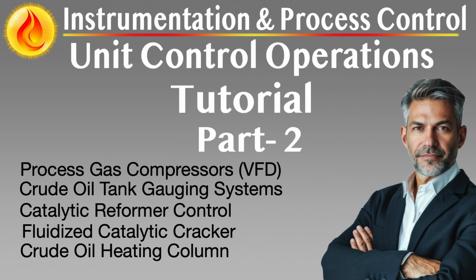Temperature control in the column is typically achieved through furnace outlet temperature manipulation, guided by feedback from column internal trays or flash zone sensors. Smart temperature profiling with multiple thermocouple levels allows the control system to infer vapor load and entrainment risk, enabling fine-tuned adjustments to heat input. This is especially critical to avoid overflashing, which could overload the pre-flash condenser or send excess light ends into the main tower, disrupting atmospheric distillation equilibrium.